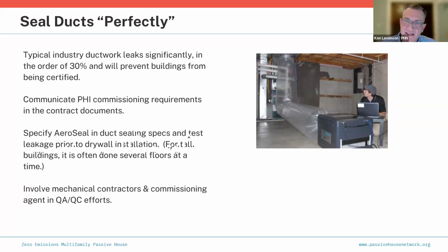But what's less talked about is the need for the ventilation ductwork to also be airtight. And many duct contractors will say, oh, we do it perfectly. We can hold a column of water with our ductwork. It won't leak. No problem. But it's really not the case, unfortunately. Typical ductwork standards in the industry, they could see 30% duct leakage. For Passive House, it's recommended to be under 3 or 2% duct leakage of the airflow.